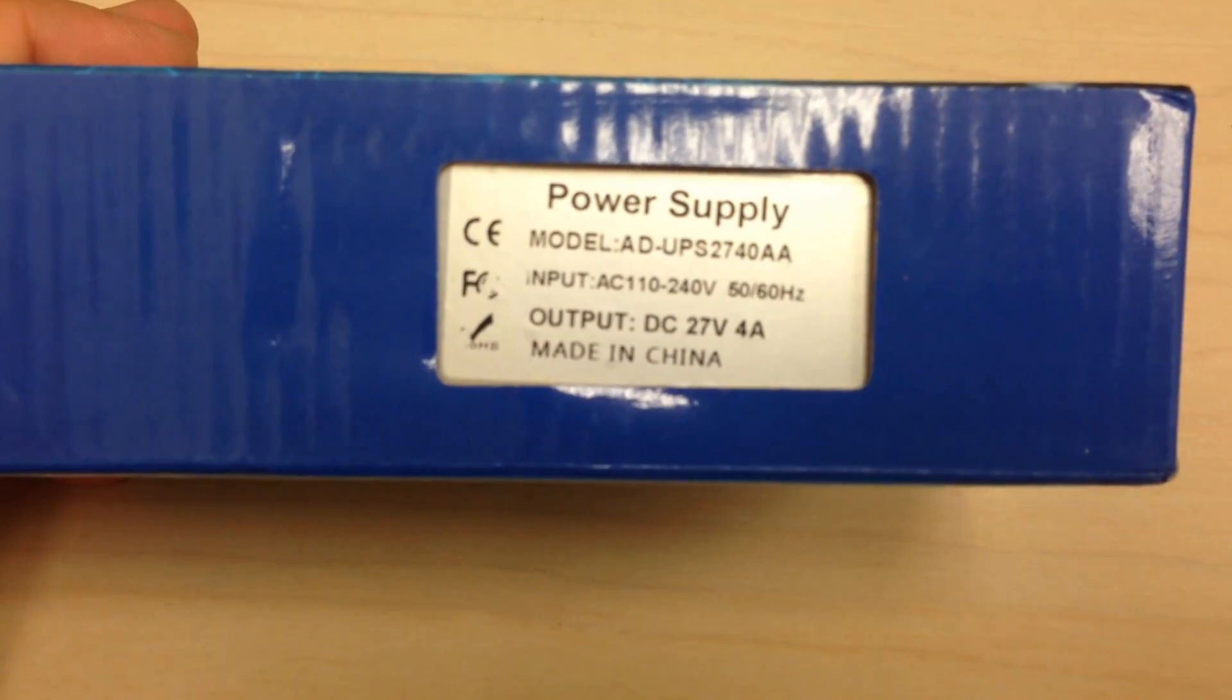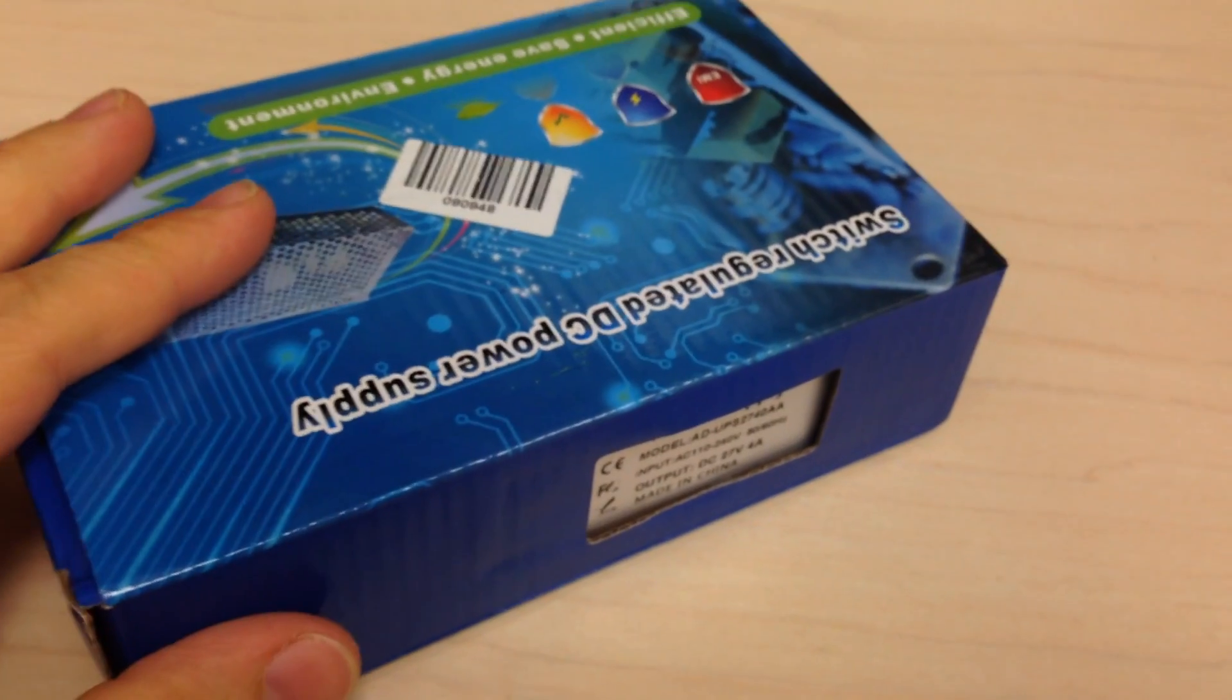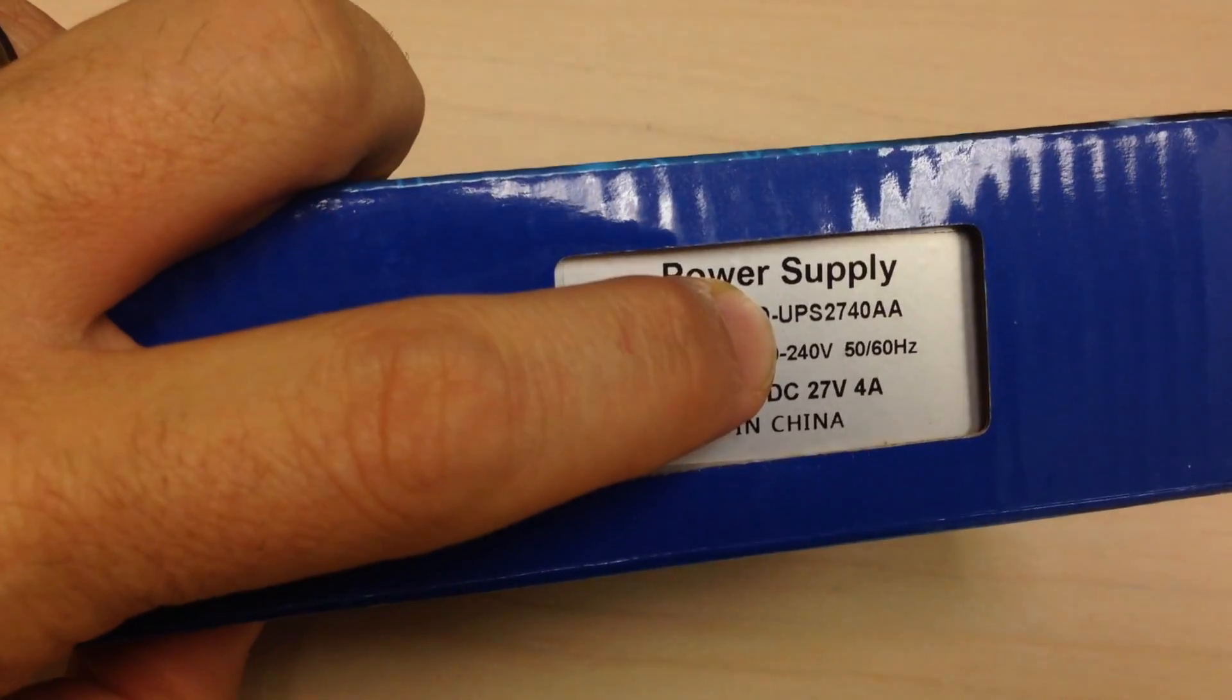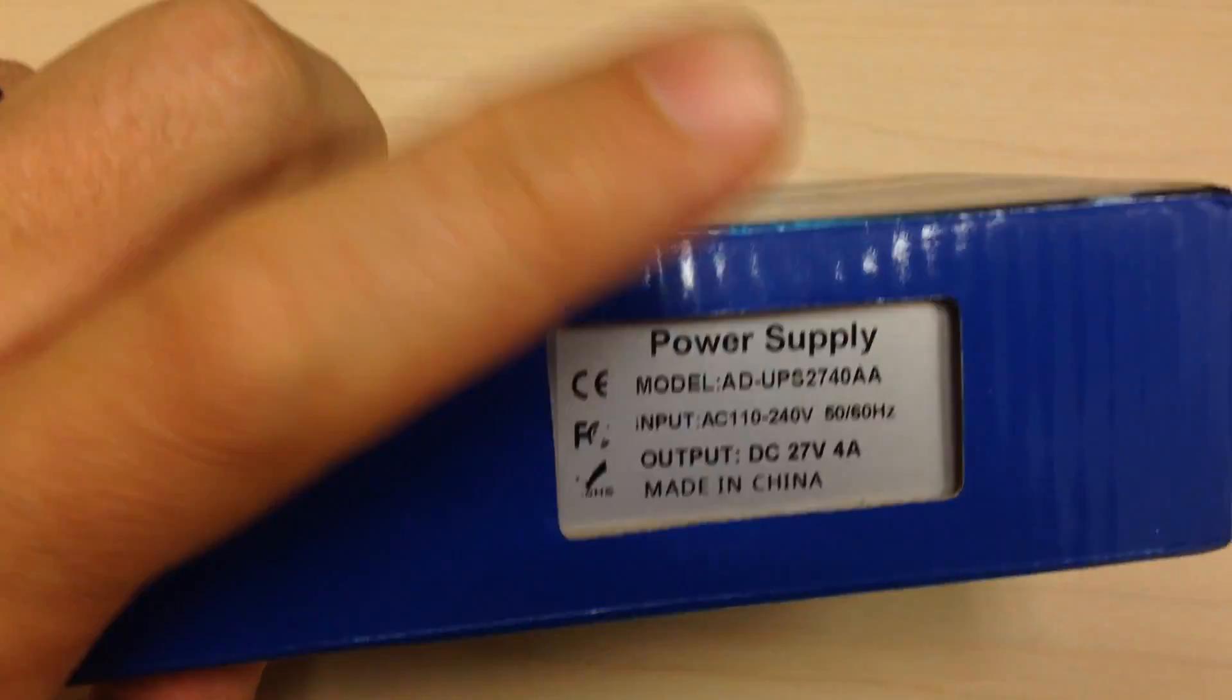This says it's a power supply, 27 volts at 4 amps, which is perfect for charging my batteries. Most of these power supplies are not going to work for this application because they will put out 24 volts. 24 volts does not charge batteries. It's less than the battery voltage. It'll actually discharge batteries if you tie them to a 24-volt power supply. But this one puts out 27 volts at 4 amps. It's actually designed to do what I'm trying to do here.